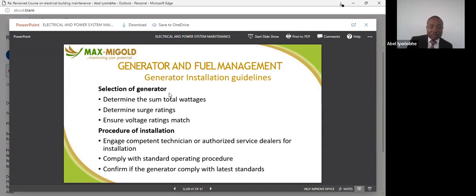If you want to see them, you check the nameplate of your equipment. They are written there. You check the voltage that is rated, the power that is rated as well. From there, you select the right generator. Power factor also, 0.8. That's the value of the power factor. You check if it's 0.8. If it's not 0.8, you ask why. Can it work? If they say it can work, tell me why I need to go for it.